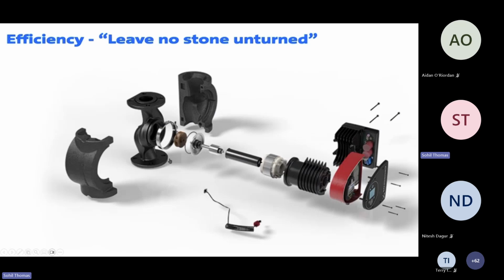So in this way, you are eliminating the PIC valves, the pressure independent control valves that you usually use for balancing purposes in these kinds of systems. And this system automatically gets balanced by using these kinds of pumps.